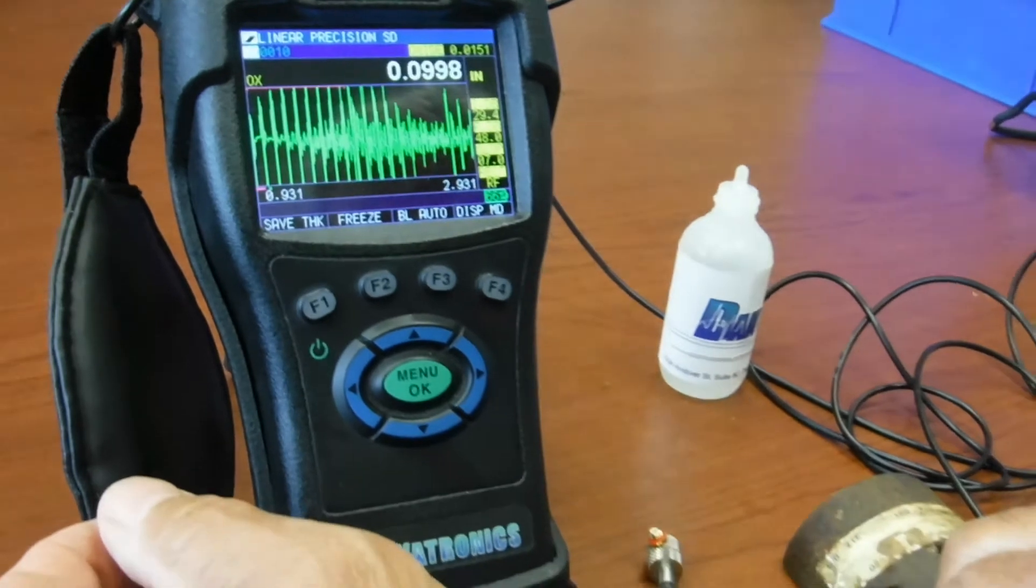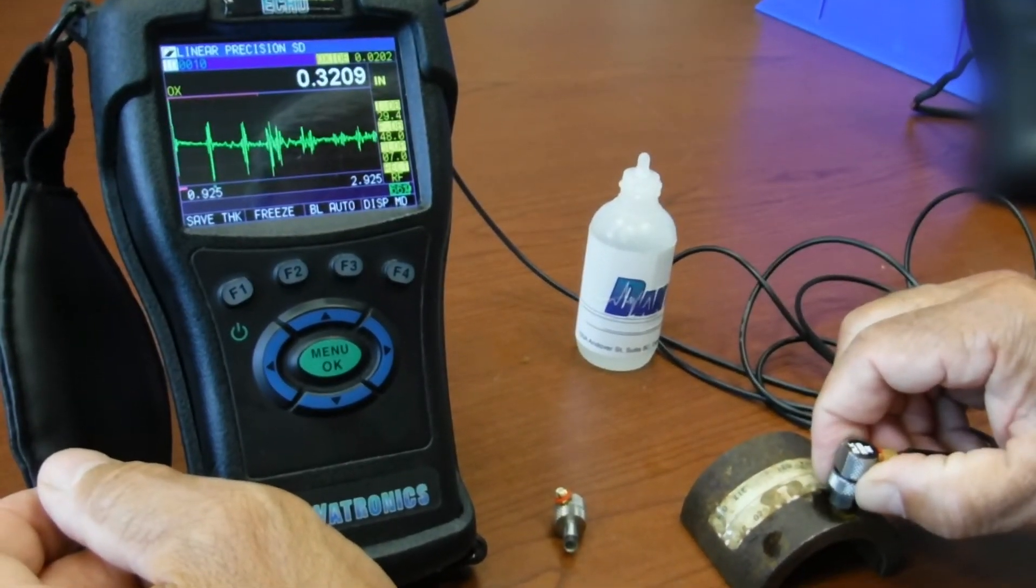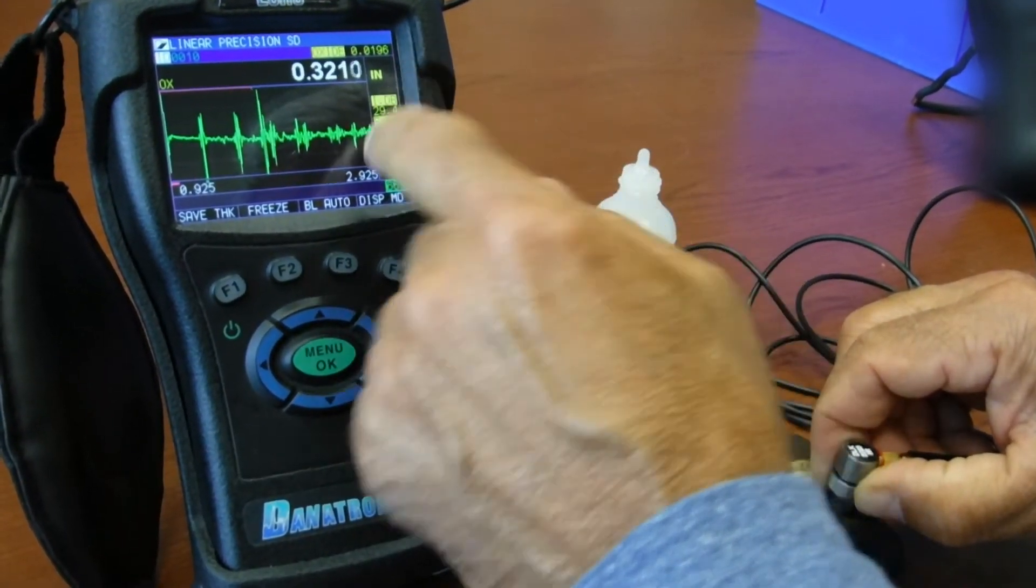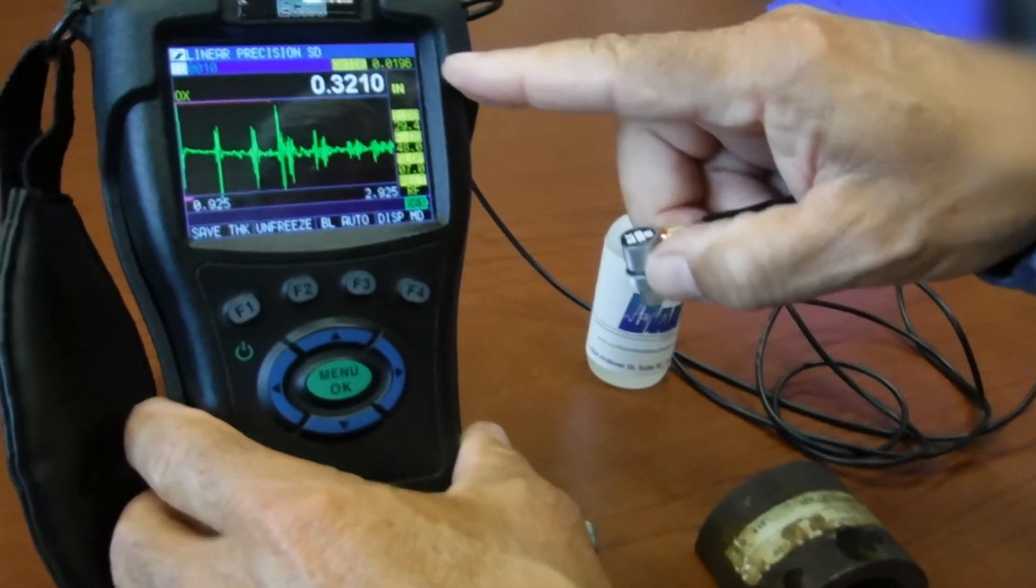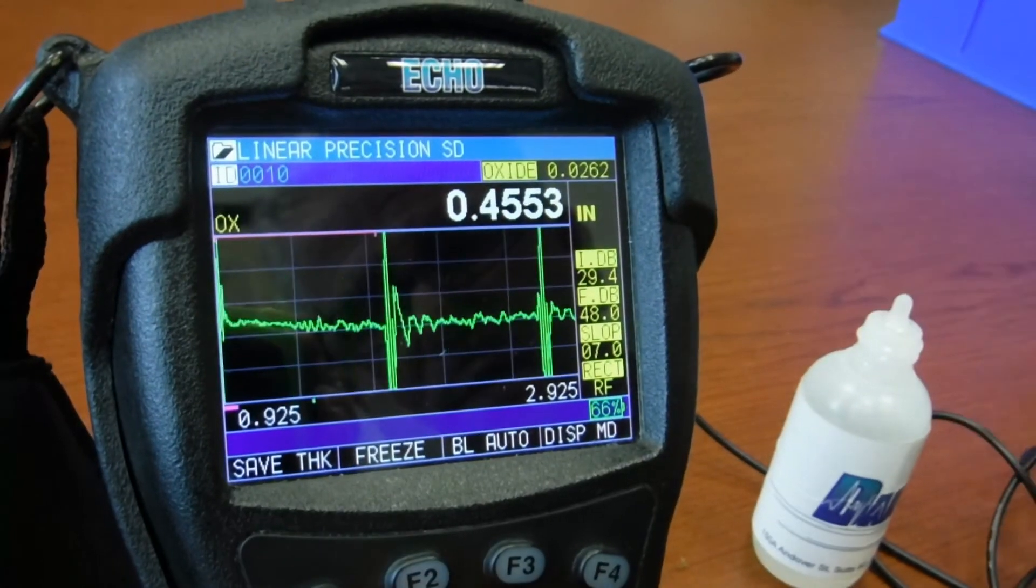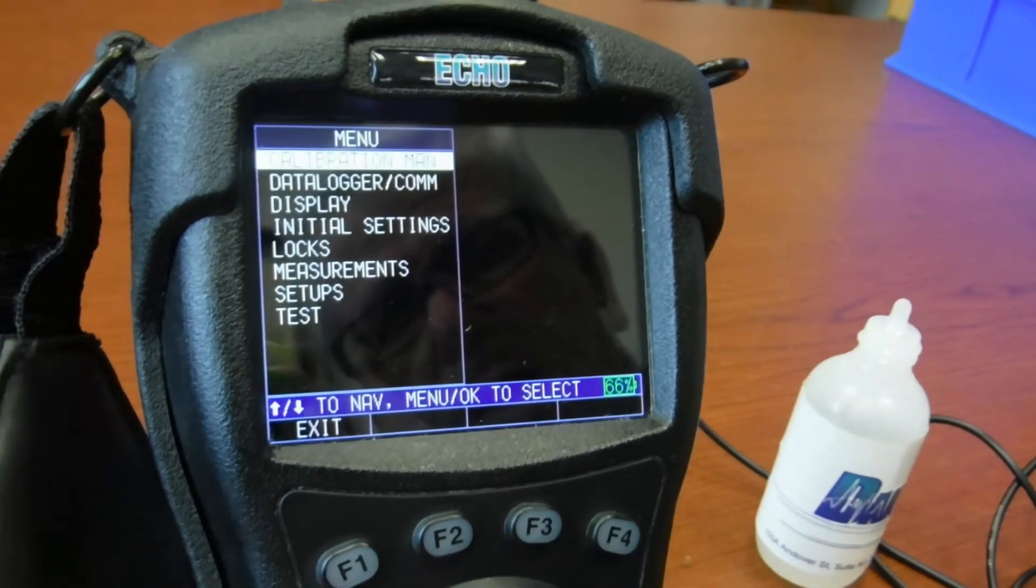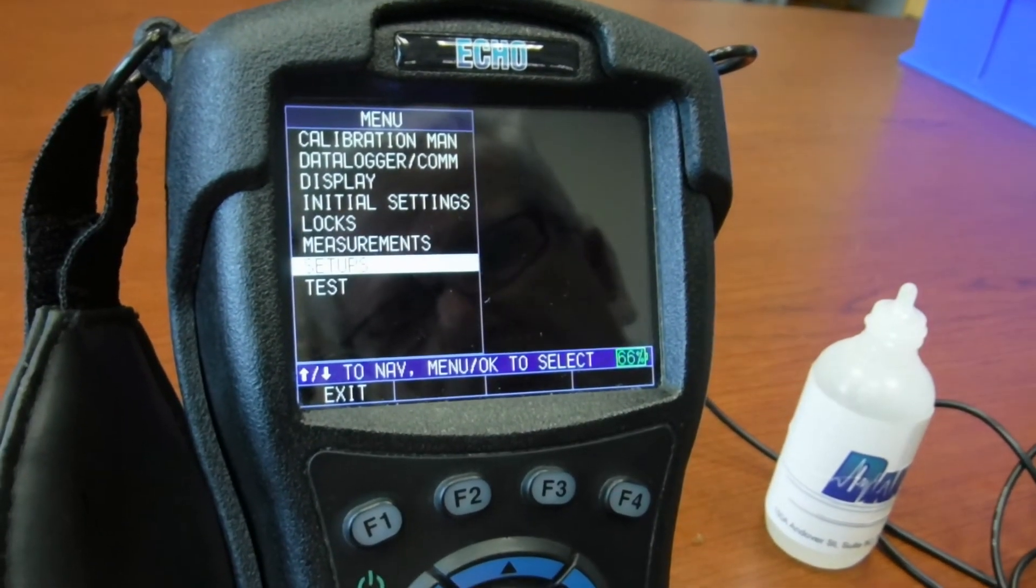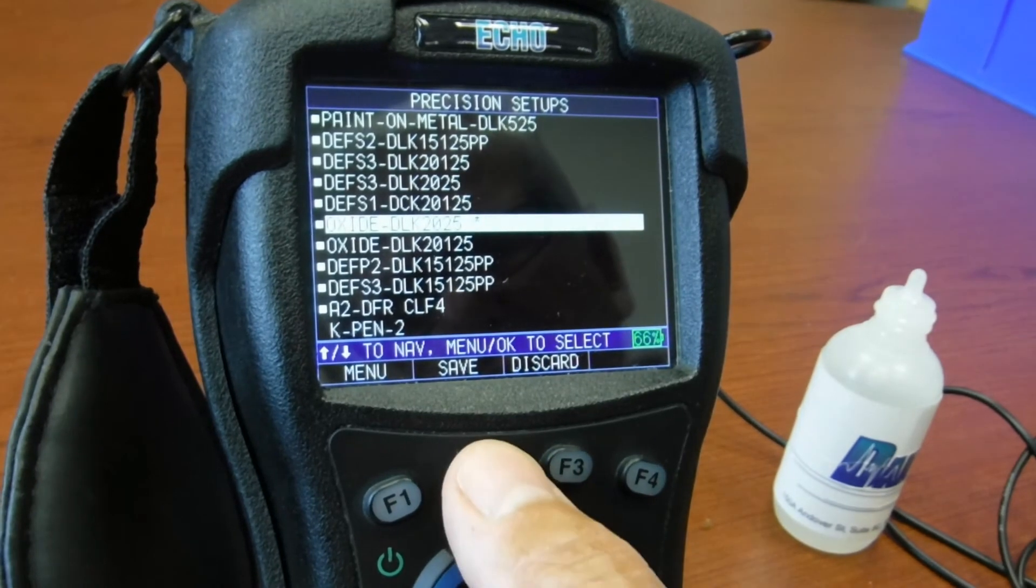At this point I'm ready to make measurements of both the tube and the oxide scale. I can freeze it so you can see the values as well. If I press unfreeze, one other thing that you can do is now go to the setup and press save and give it a name.